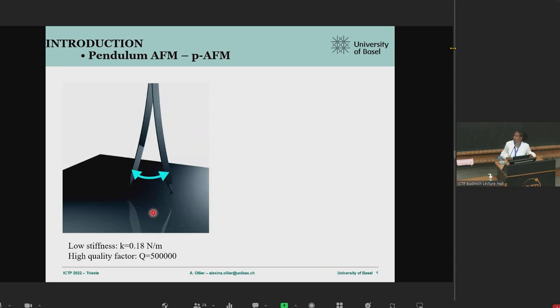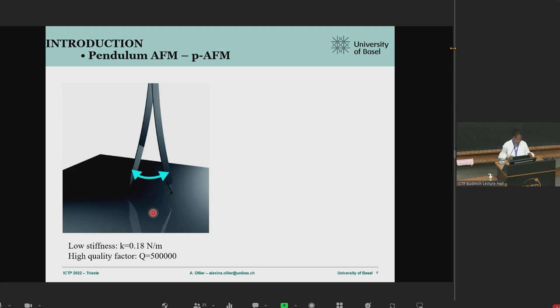Our system is an atomic force microscope, but our geometry is different — we call it pendulum, because the cantilever is perpendicular to the sample surface and oscillates like a small pendulum over the sample surface. This geometry avoids snapping of the tip onto the sample surface and enables us to use cantilevers with low stiffness — very small spring constant. Basically, it's a contact cantilever that we use for non-contact measurements, and we have a high quality factor. These two parameters are the main parameters we can tune to increase our sensitivity.